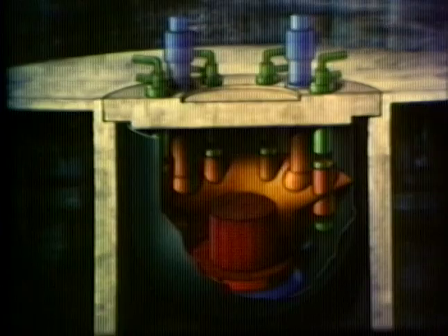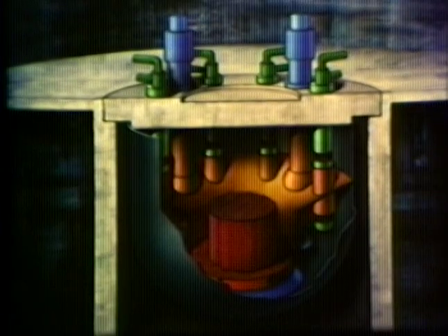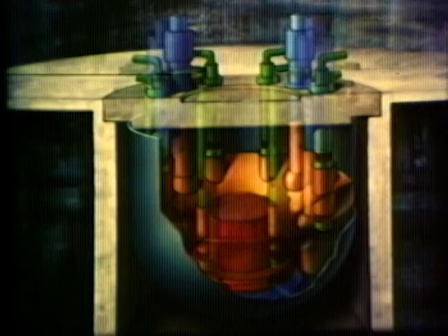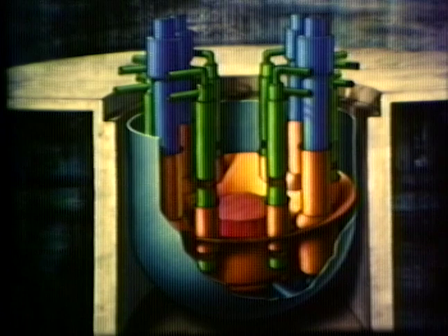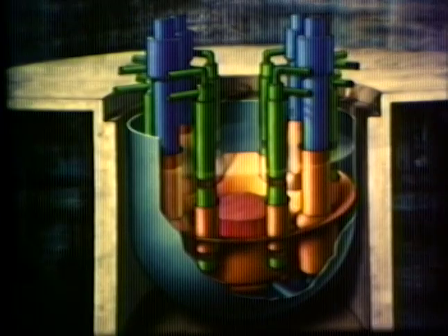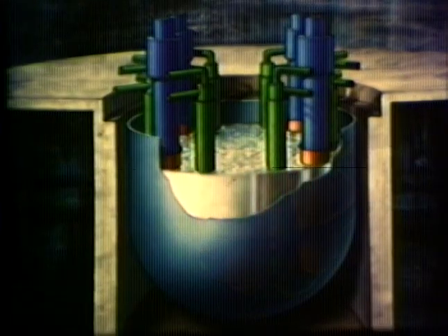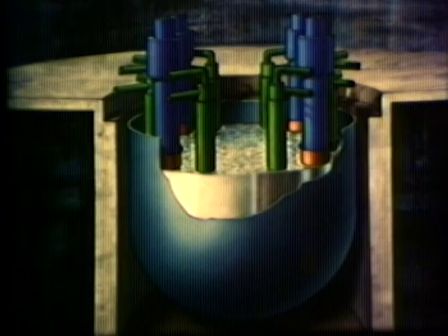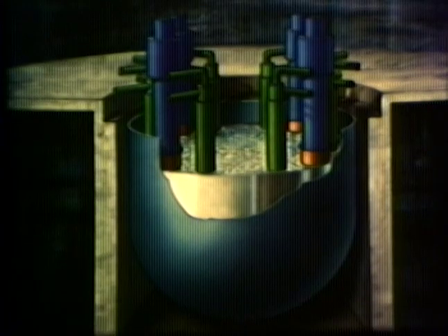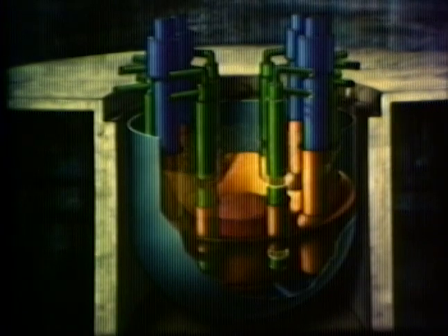The primary sodium pumps and the intermediate heat exchangers are installed in special shafts. A total of 8 heat exchangers and 4 pumps are provided to remove the 3,000 megawatts of heat released in the core by circulating the primary sodium. The main vessel contains 3,500 tons of this sodium, which need not be pressurized because it remains well below its 900 degrees centigrade boiling point. At the hottest spot, at the core outlet, the primary sodium attains only 550 degrees centigrade, the temperature at which it reaches the intermediate heat exchangers.